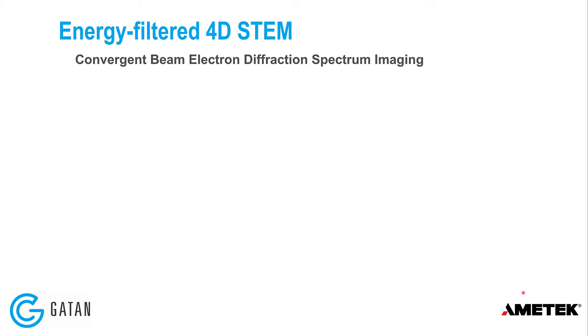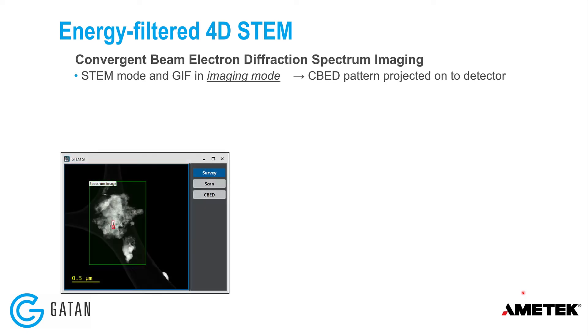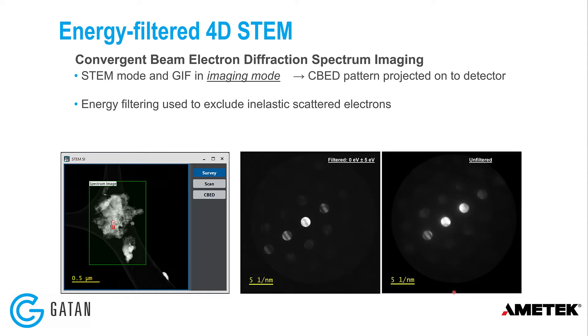4D STEM is convergent beam electron diffraction done in spectrum imaging. In STEM mode, the GIF is in imaging mode, so we're looking at a convergent diffraction pattern on the detector. Energy filtering is used to exclude inelastically scattered electrons, which improves contrast and diffraction spot sharpness, aiding interpretation of the diffraction data.